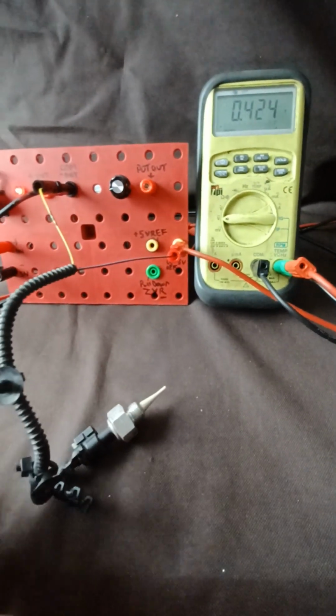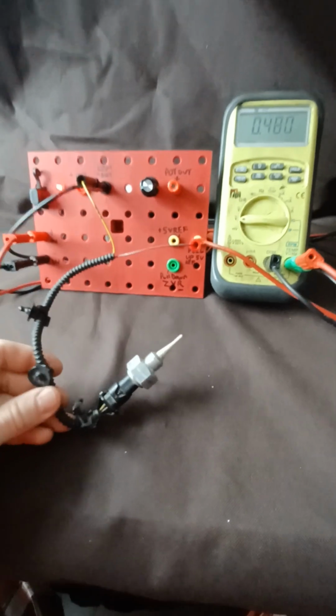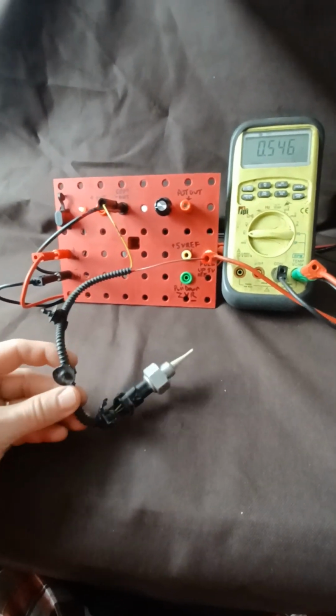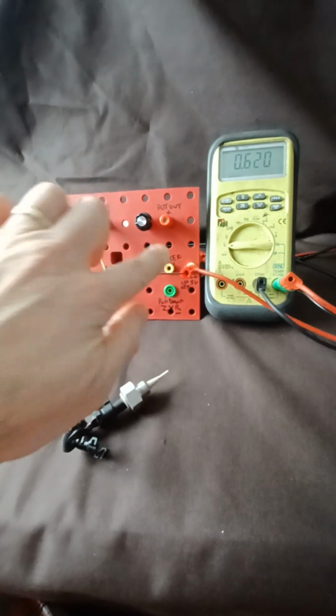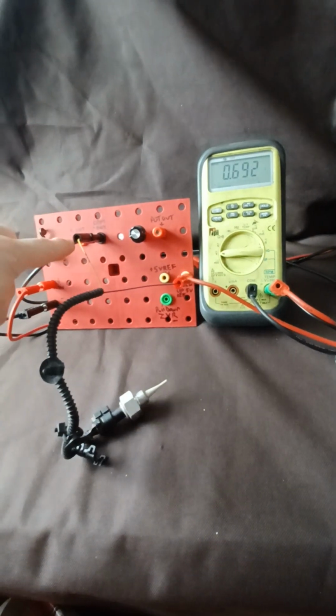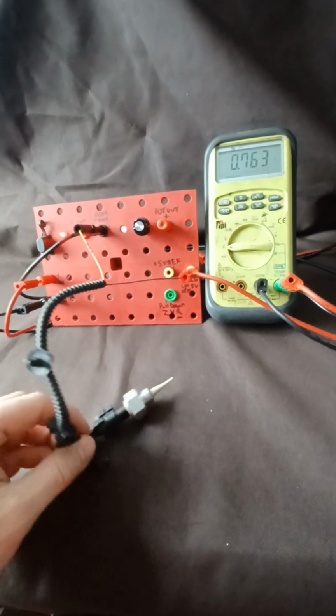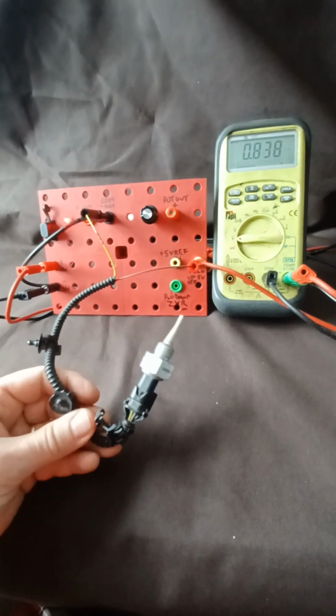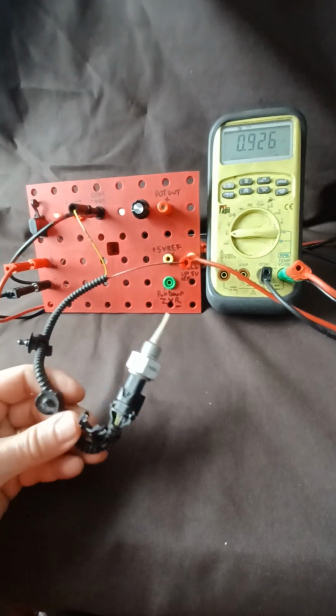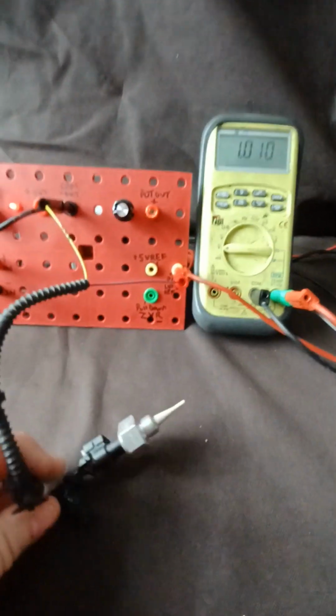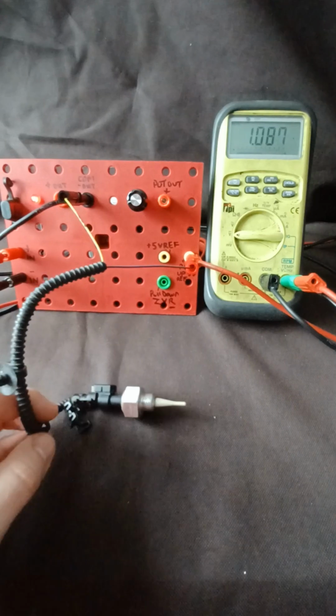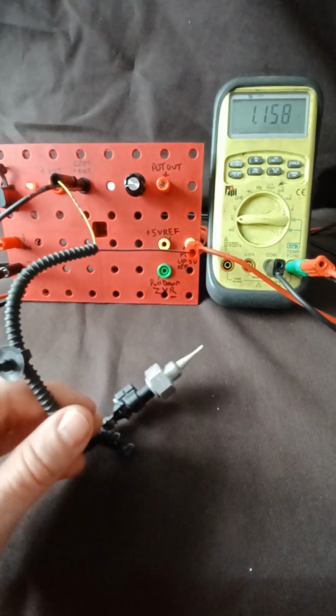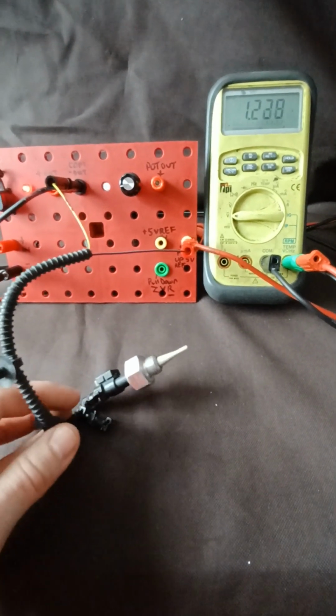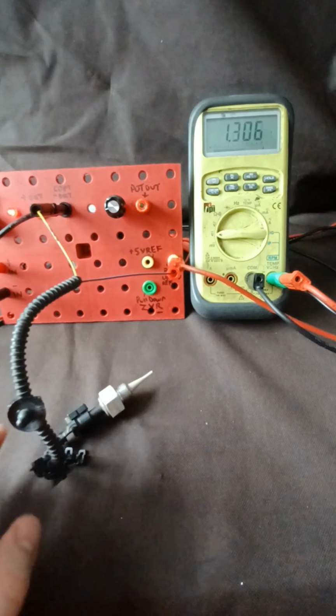And that's by design. It's meant to be that way, because if it ever reached 0 resistance, that would be equivalent to us installing a wire or shorting to ground between positive and ground. We don't want it to be 0 resistance, or that would actually throw a different fault in the ECU. That would be a problem. So no matter how hot or cold that temp sensor gets, or any other sensor gets, it should never have no resistance to it at all.